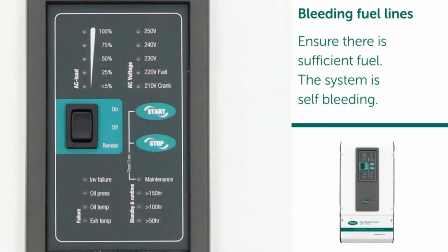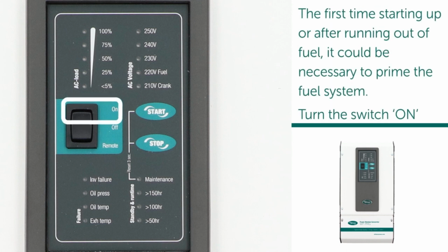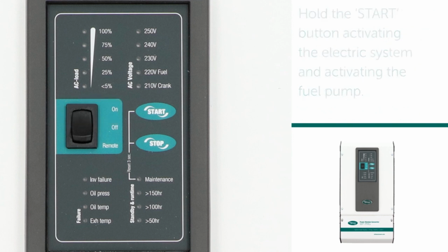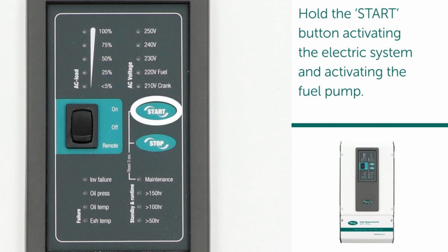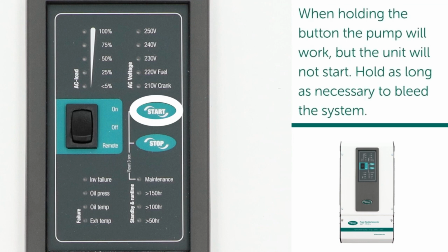Bleeding fuel lines. Ensure there is sufficient fuel. The system is self-bleeding. The first time starting up or after running out of fuel, it could be necessary to prime the fuel system. Turn the switch on. Hold the start button, activating the electric system and activating the fuel pump. When holding the button, the pump will work, but the unit will not start. Hold as long as necessary to bleed the system.